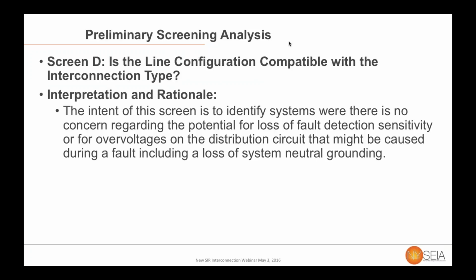The intent of this screen is simply to ensure that your interconnection is compatible with the distribution system and that you don't introduce the potential for losing the ability to identify faults, weakening their sensitivity to fault detection, or ground fault over voltage on the actual distribution system as well.